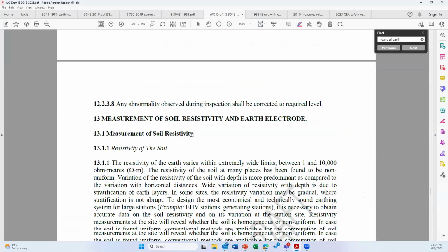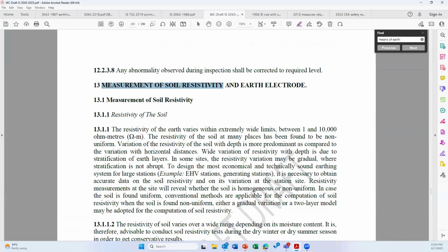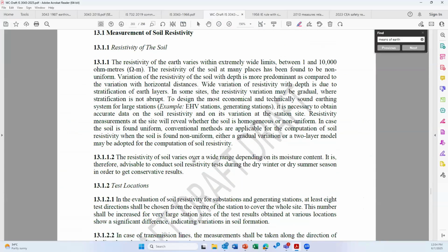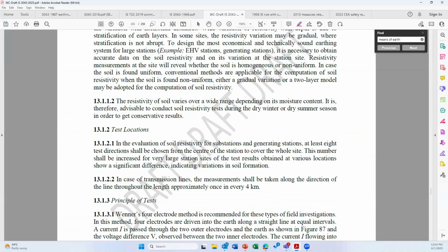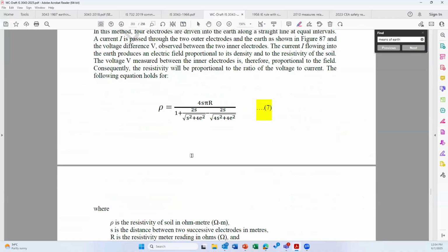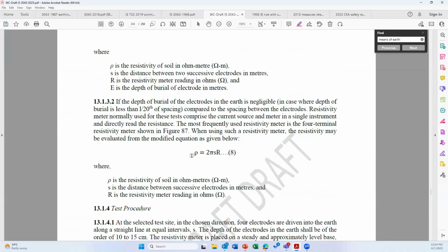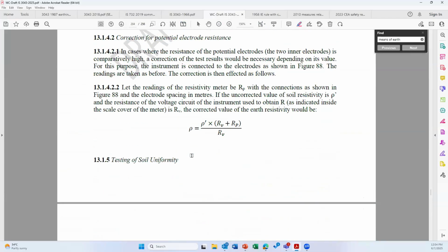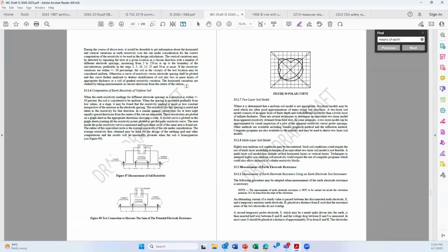Then going to clause number 13, which talks about measurement of soil resistivity and earth electrode. As I said, the reliance on soil for the purpose of fault return is very much less nowadays, but still the old calculations are being followed. But a lot of improvements happened in this particular chapter. The new figures from IEC 60364 are being included, especially to measure the earth electrode resistance.